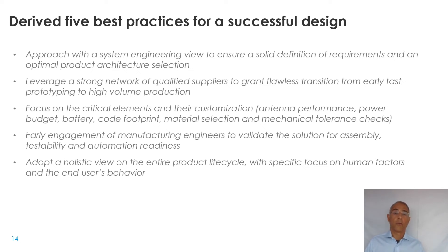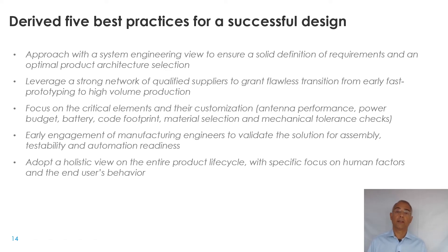Third: focus on specific critical items in your smart syringe design — battery selection, the antenna, and the firmware footprint, especially for services defined later such as manufacturing test services and security and safety services. Also address mechanical design and tolerances, ensuring they are kept under control from both a mechanical and manufacturing standpoint, and that tolerance stack-up is properly managed.